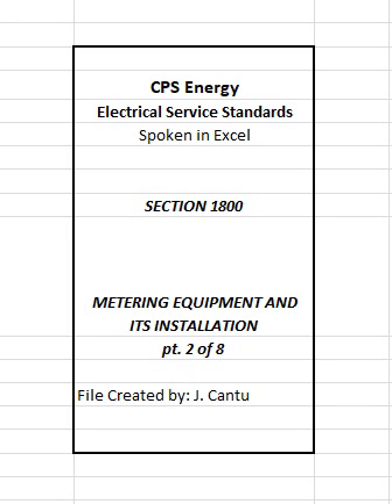D. For services supplied by pad mount transformers, the CT/VTs will be located within the secondary compartment of the transformer. Refer to figures 1001 and 1002 and section 1000. E. Exception. On transformer installations of 300 kVA or less, CPS Energy may require the use of self-contained metering equipment on a metering equipment rack or directly on the building or structure.